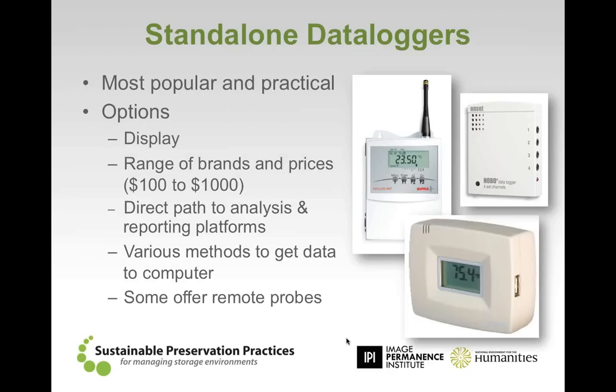The battery life on that $70 logger, when you looked at it, was dependent on the sampling rate, and it said it would last 1 year. But when I really started looking at it, sampling every 5 minutes lowered the logger lifespan to, I believe, almost 3 months. So it's important you look at that. 1 year's worth of data collection is going to give you an accurate TWPI for your space. It's going to show you the seasonal changes within your space as well, or how your systems handle seasonal change. So you want to make sure you get that 1 year's worth of data. I'll say it a couple more times, 1 year's worth of data.